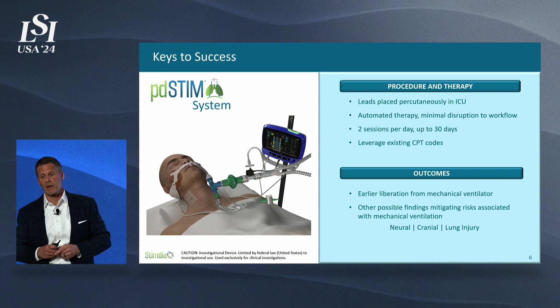Also attached to that console is an integrated flow and pressure transducer, which you can see here, that goes in the ventilatory circuit itself. Our components are the lead, which we have manufactured, and then the console itself. The flow pressure transducers are off-the-shelf components. The reason we've got those in line here is so that we can be agnostic to any ventilator that's out there. What this allows us to do is trigger our therapy within milliseconds of detection of inspiration, and then we stop our therapy at expiration, which is important because dyssynchrony and asynchronous events are a common problem with respiratory therapists out there.